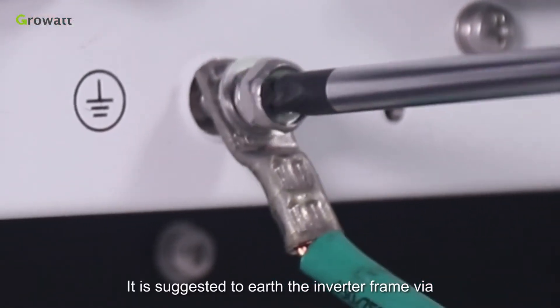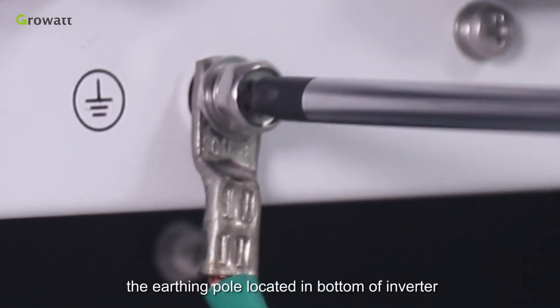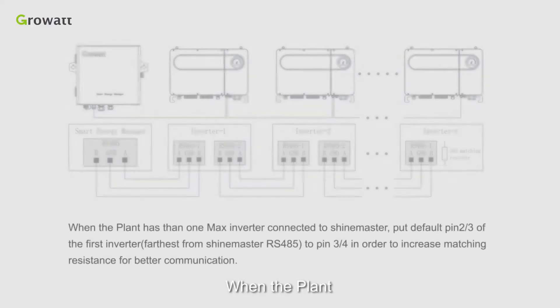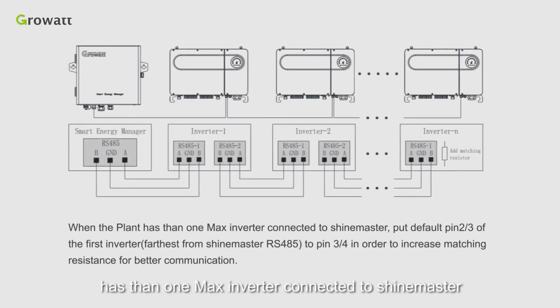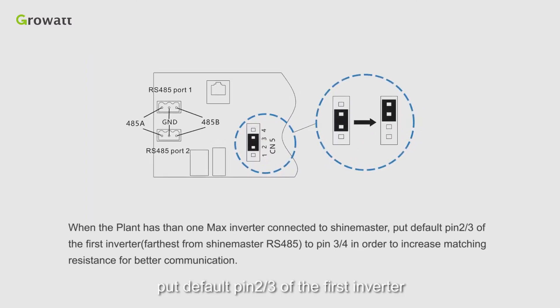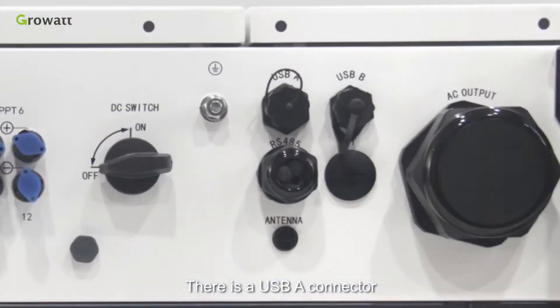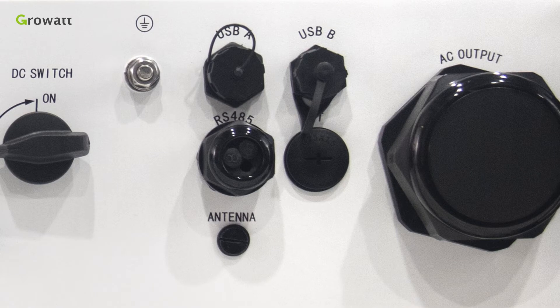It is suggested to earth the inverter frame via the earthing pole located at the bottom of the inverter. When the plant has more than one Max inverter connected to the Shine Master, put default pin 2/3 of the first inverter (farthest from Shine Master RS485) to pin 3/4 to increase matching resistance for better communication. There is a USB-A connector, USB-B connector, and RS485 socket on the bottom of the inverter.